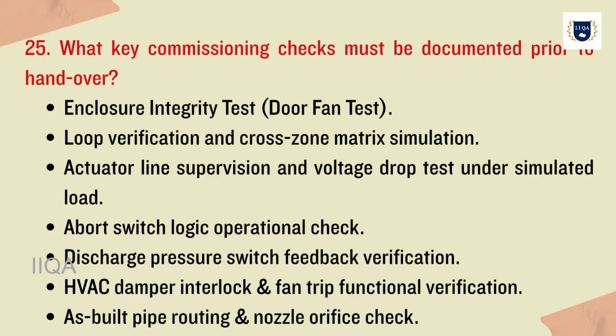25. What key commissioning checks must be documented prior to handover? Enclosure integrity test, door fan test, loop verification and cross-zone matrix simulation, actuator line supervision and voltage drop test under simulated load, abort switch logic operational check, discharge pressure switch feedback verification, HVAC damper interlock and fan trip functional verification, as-built pipe routing and nozzle orifice check.